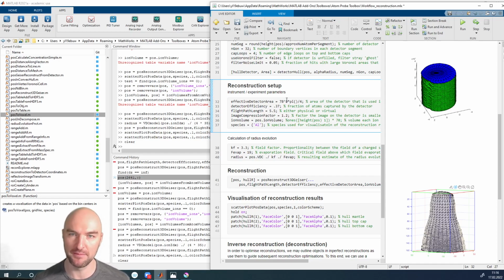This is the diameter of the detector. If you buy the Hamamatsu microchannel plates, the funnel ones, you can only get up to 80 millimeters, but 80 millimeters is sort of large but standard. The older commercial atom probes used the 78, 80 millimeter detectors, and the new ones more or less have to use them because it's the largest funnel MCPs that you get, at least the straight flight path ones. With the reflectron ones, you have smaller ones.